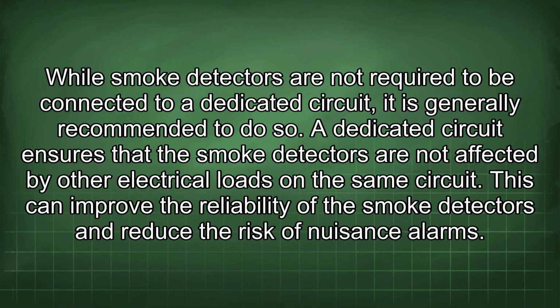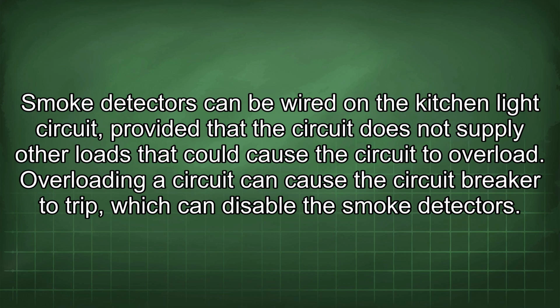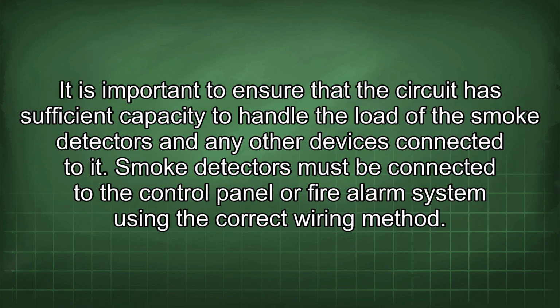While smoke detectors are not required to be connected to a dedicated circuit, it is generally recommended to do so. A dedicated circuit ensures that the smoke detectors are not affected by other electrical loads in the same circuit. This can improve the reliability of the smoke detectors and reduce the risk of nuisance alarms. Smoke detectors can be wired on the kitchen light circuit, provided that the circuit does not supply other loads that could cause the circuit to overload. Overloading a circuit can cause the circuit breaker to trip, which can disable the smoke detectors. It is important to ensure that the circuit has sufficient capacity to handle the load of the smoke detectors and any other devices connected to it.